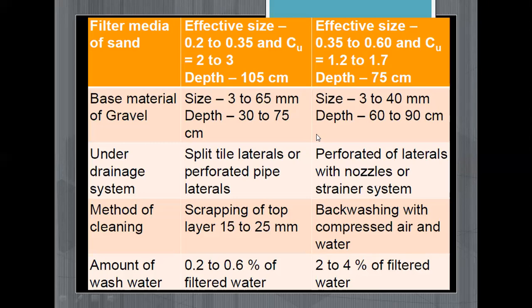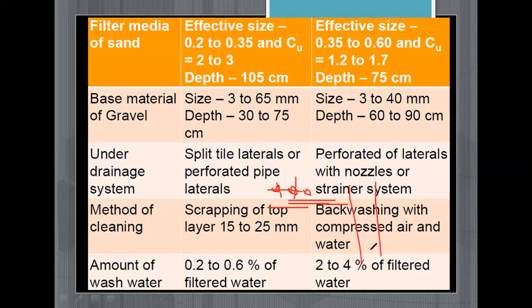The underdrain system in the slow sand filter consists of split tile laterals or perforated pipe laterals. In the rapid sand filter it is perforated laterals with nozzles or a strainer system. Perforated pipes are lateral pipes having openings or holes through which water enters inside the pipe, and these lateral pipes are connected to the main drain or central drain.